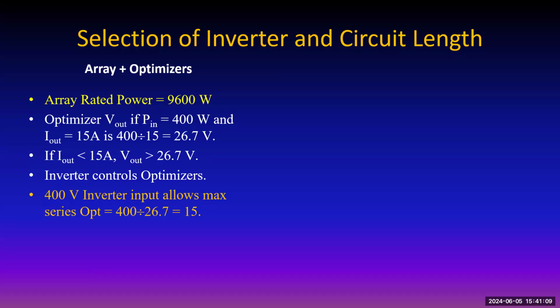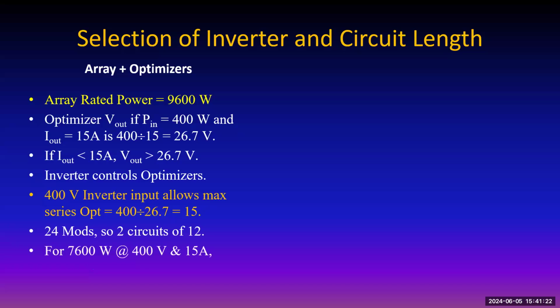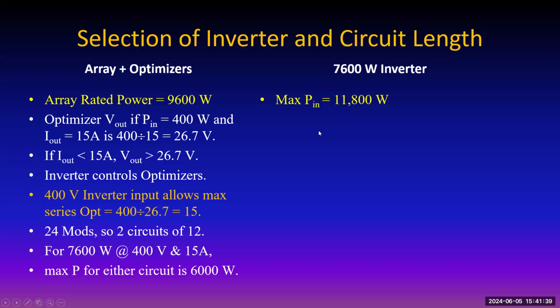That's 15. So you can't have more than 15 optimizers. Otherwise, at maximum current, it's going to overload the thing. 24 modules, two circuits of 12, 7,600 watts at 400 volts, 15 amps. That leaves 6,000 watts for, this is the inverter, is a 7,600 watt inverter.